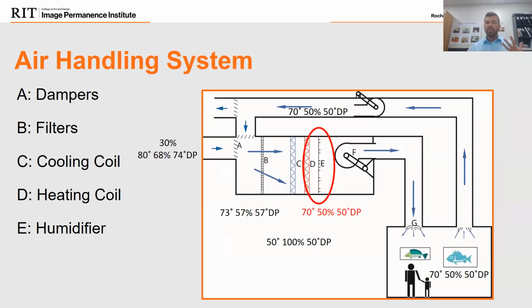So we've crossed the humidifier. Since our relative humidity condition and dew point are perfect, we don't want to change anything. Our condition stays the same. If this were a drier season, maybe a winter month, we may want to add moisture. If our dew point was too low, we may want to top it off, add a little bit of moisture here. But our conditions were good. We don't need to make any change.